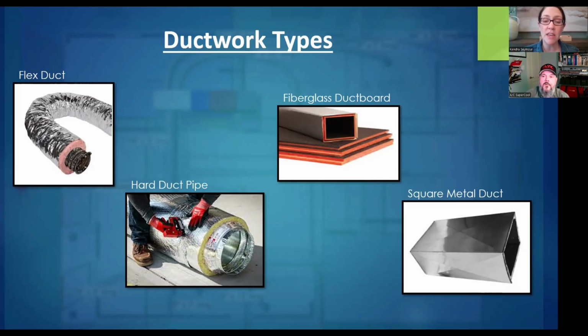I think it's worth talking about because you mentioned several important things — if it has some sort of microbial growth, which is different than settled spores, that's a systemic issue you need to get to the bottom of. The fiberglass duct board and the square metal duct board with that insulation needs to be replaced. I've seen people attempt to clean that with negative pressure, and they end up getting fiberglass in the air, and that's a whole other thing. So it's a big red flag.